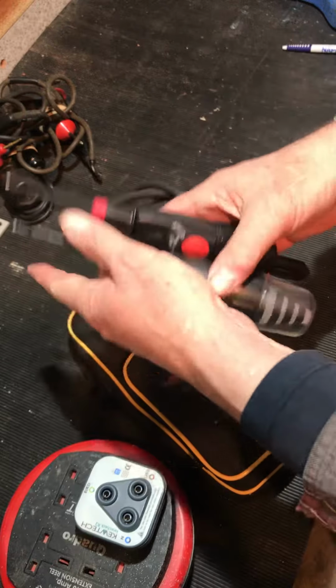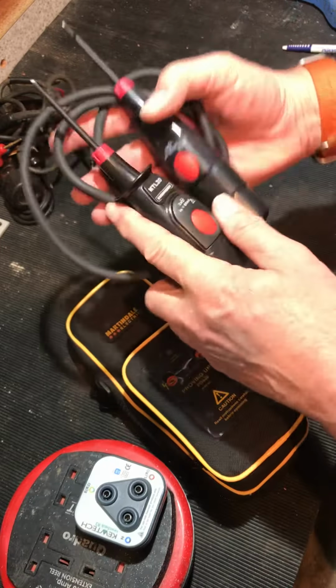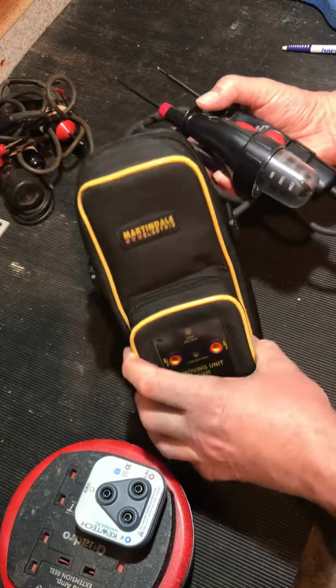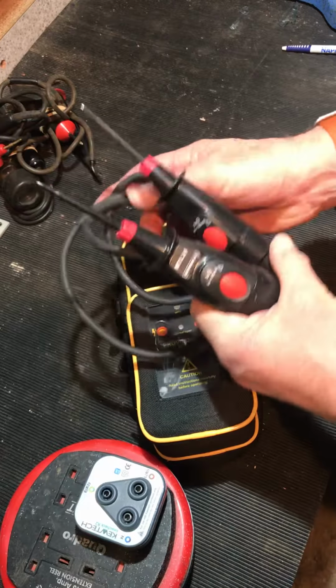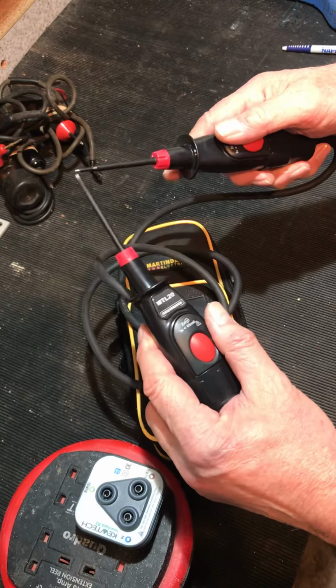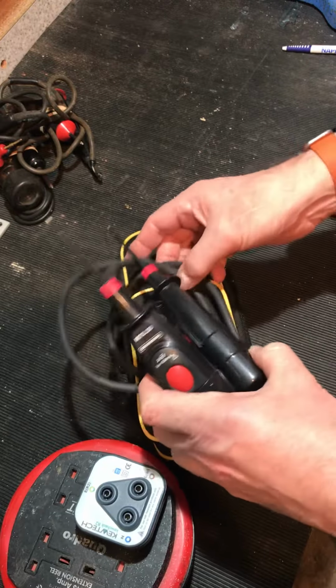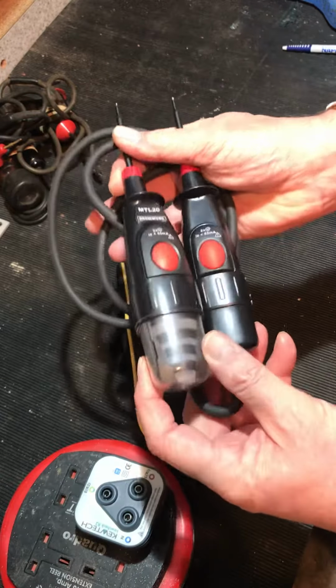So that is the favourite of people in industrial markets, maybe DNOs. It does add quite a packet to your tool bag, and some people are not going to like the fact that it's a one-shot tester. It doesn't do continuity, it only keeps you alive. Some people don't like it. Of all my testers, I think that is my favourite.